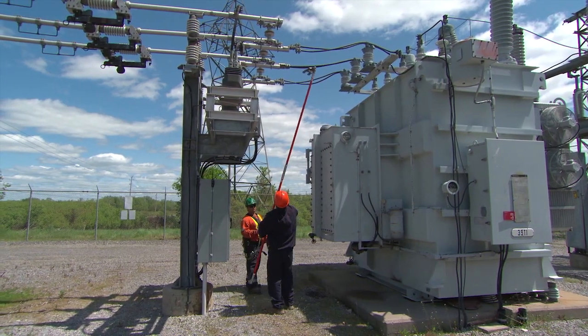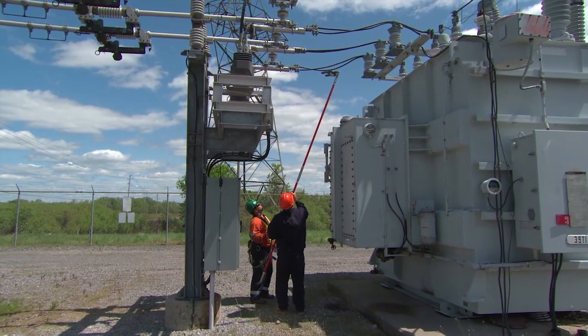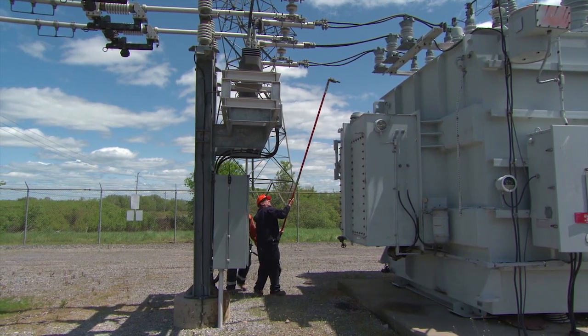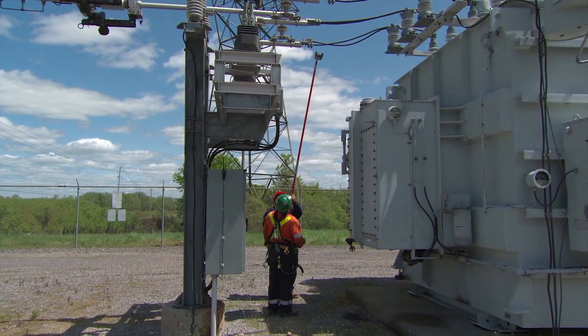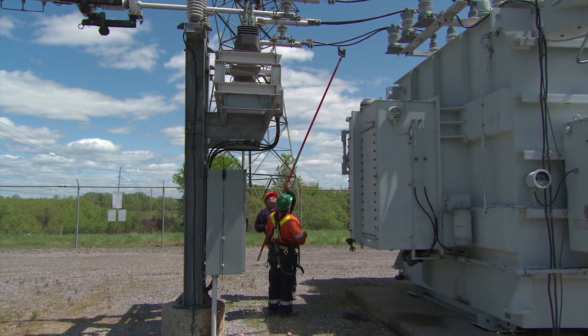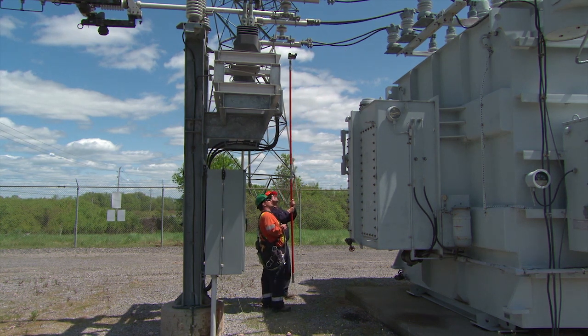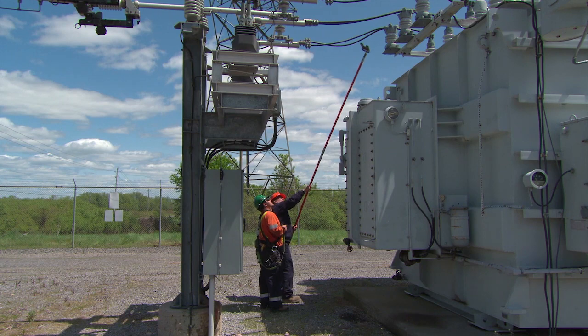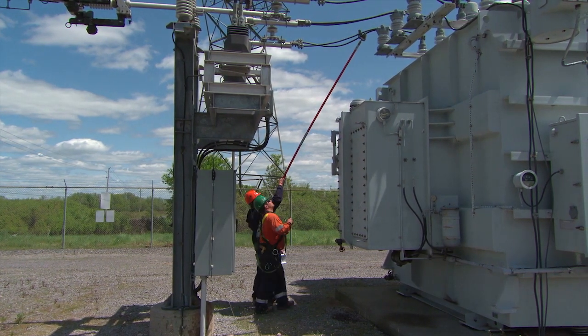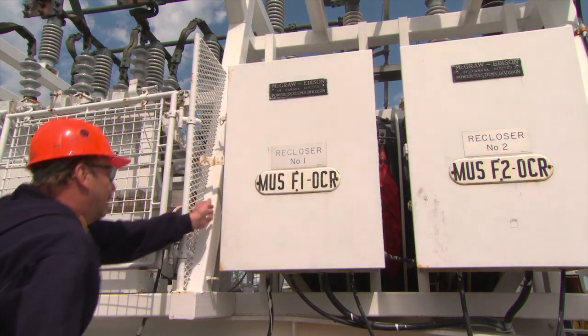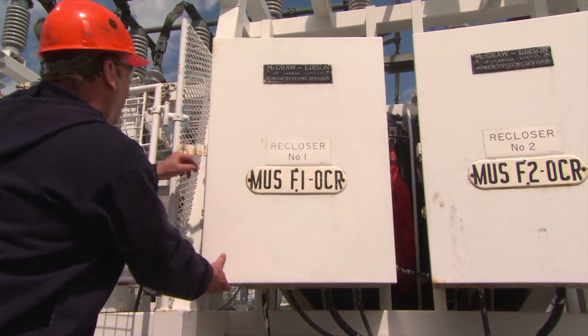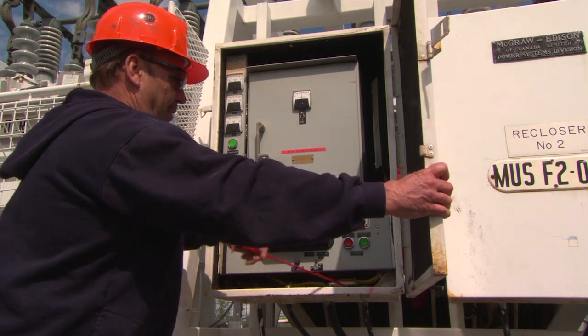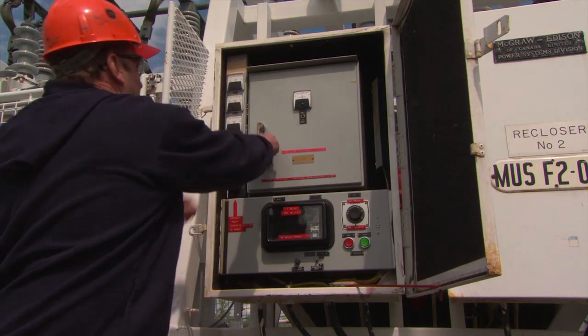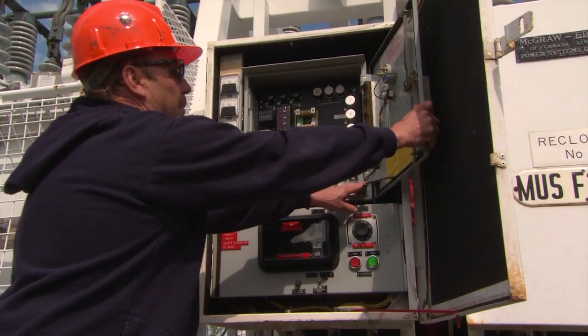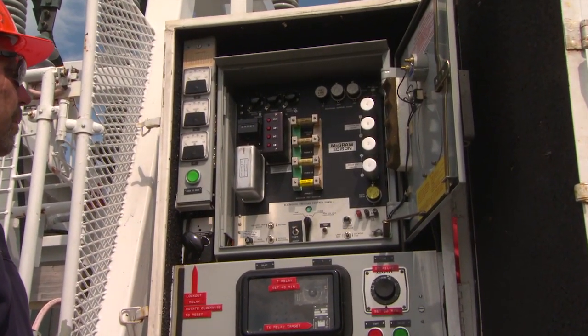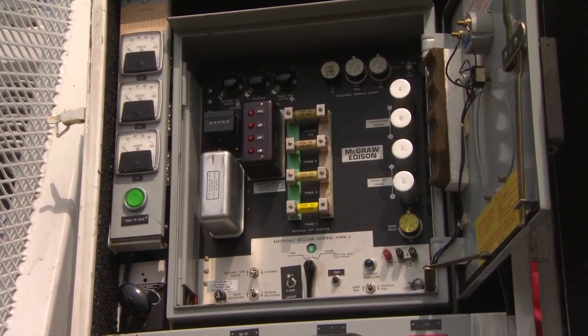The MUS recloser trip resistor must be set to 560 amp phase trip with the ground trip blocked. The MUS high-voltage fuses protect the MUS and the DS low-voltage bus up to the DS low-voltage feeder reclosers. No coordination is required between the MUS high-voltage fuse and the MUS low-voltage reclosers. At stations with a primary rating of 27.6 kV, the 400 amp phase trip and 280 amp ground trip resistors are the maximum size that can be used in the MUS feeder reclosers. This will provide the proper coordination with the MUS high-voltage fuses.